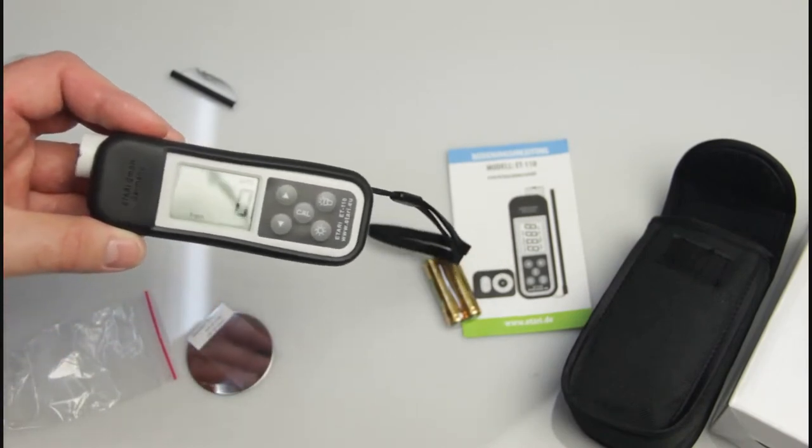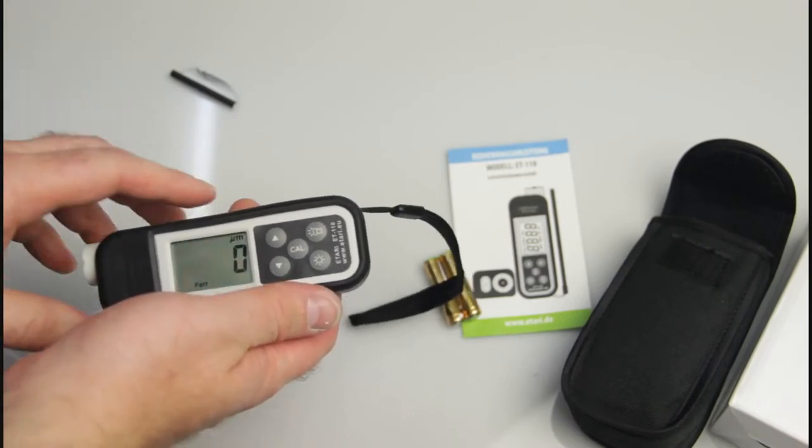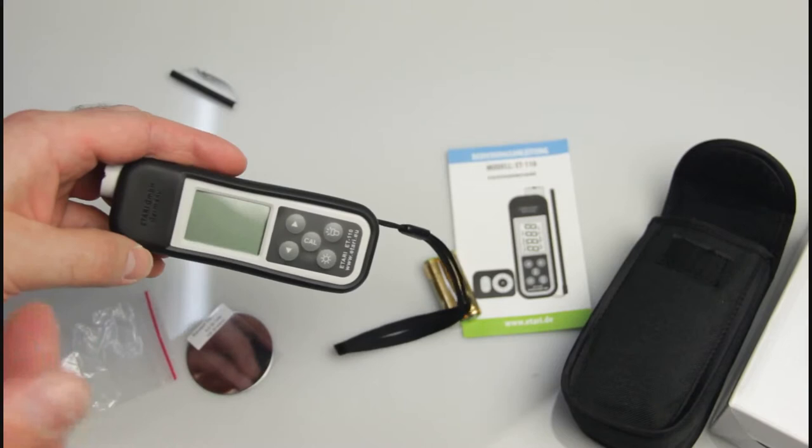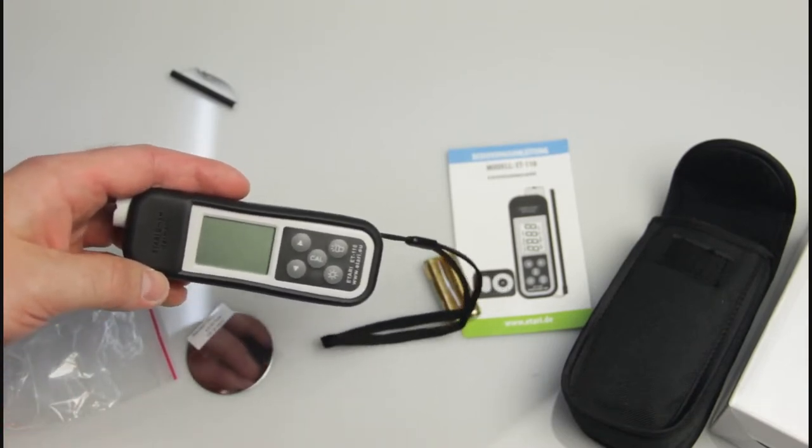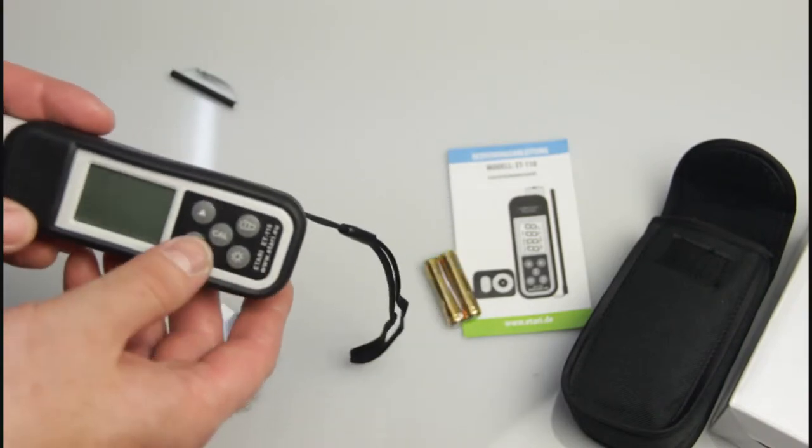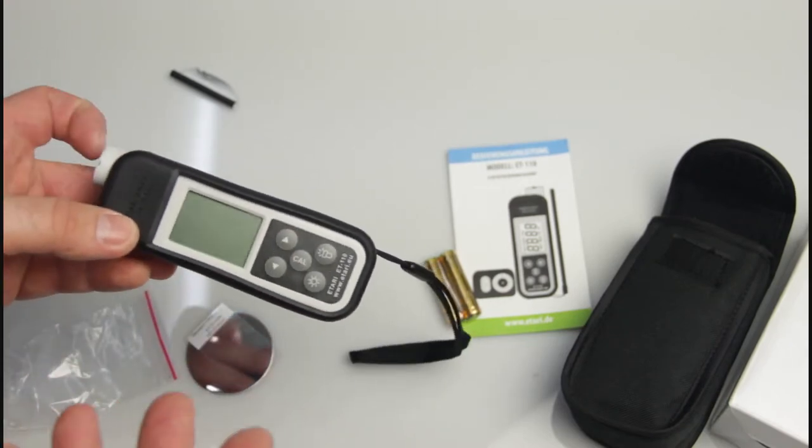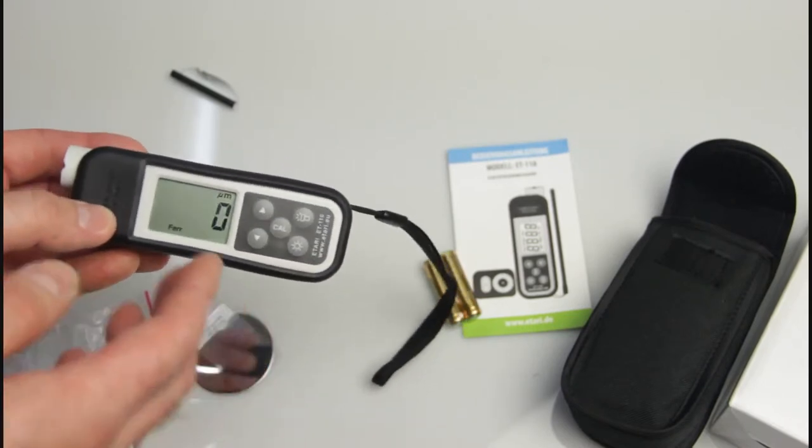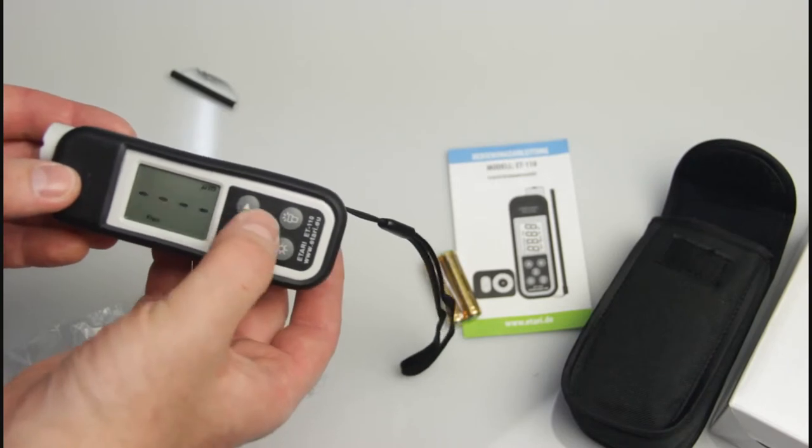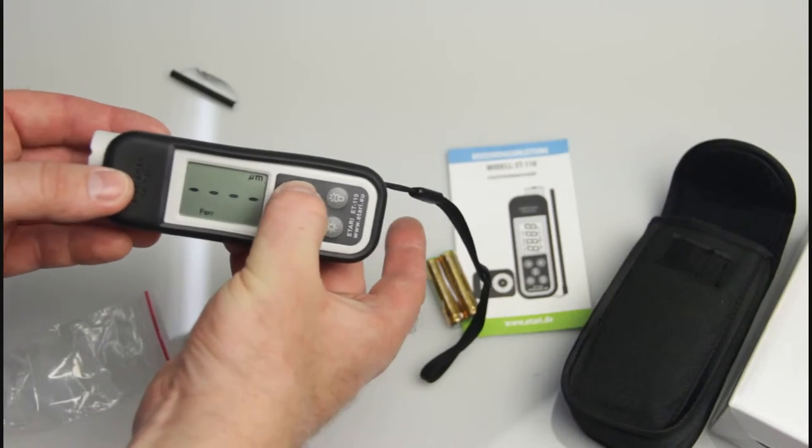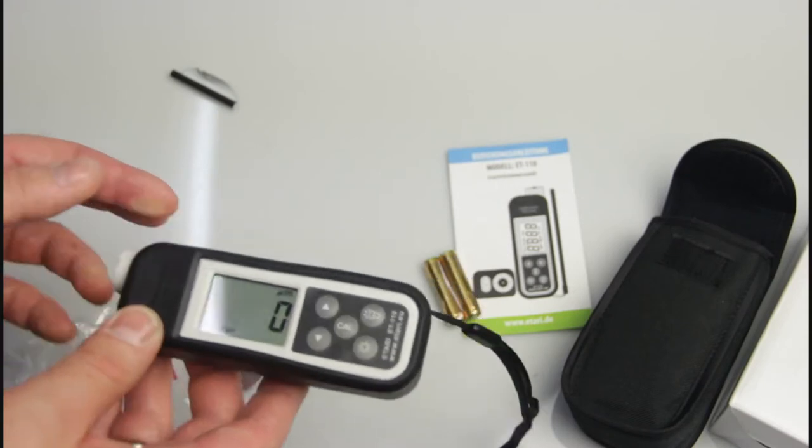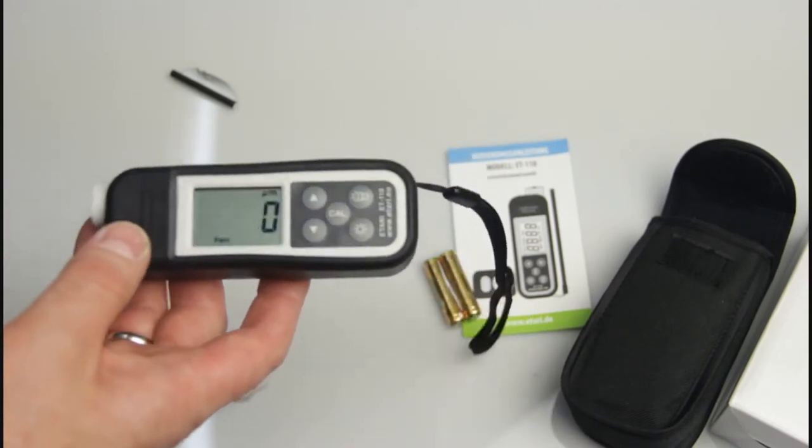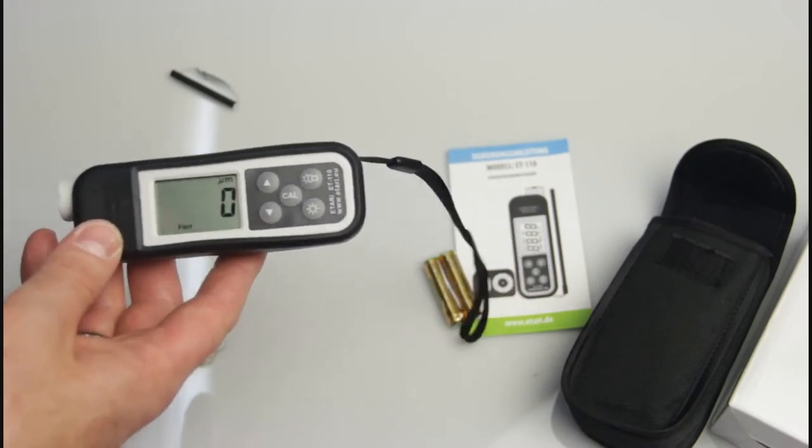Sometimes there is situation that the gauge shows wrong result and you think it's lying. Maybe something happened inside of the firmware and you can reset to the factory default settings. How to do it? Turn the gauge on and turn the arrow up button for about 4 seconds. Here it is, it's reset.